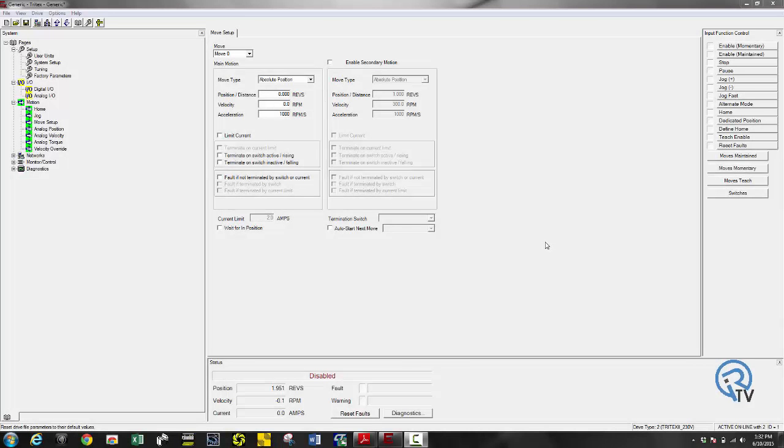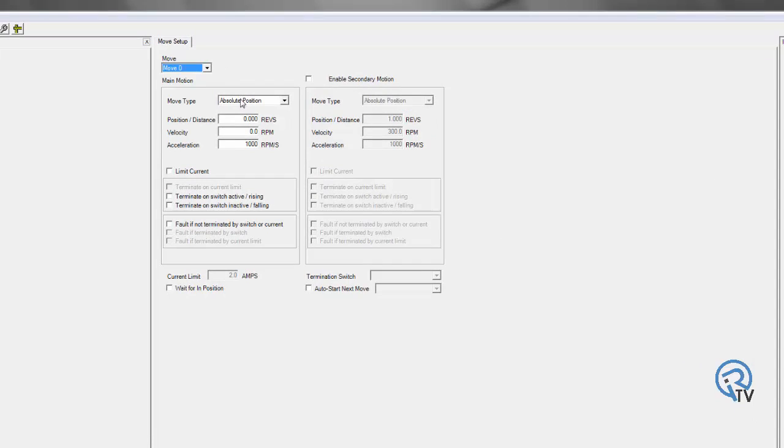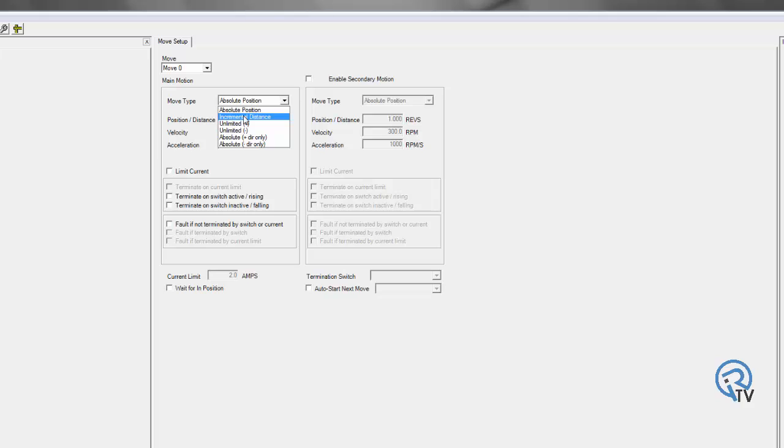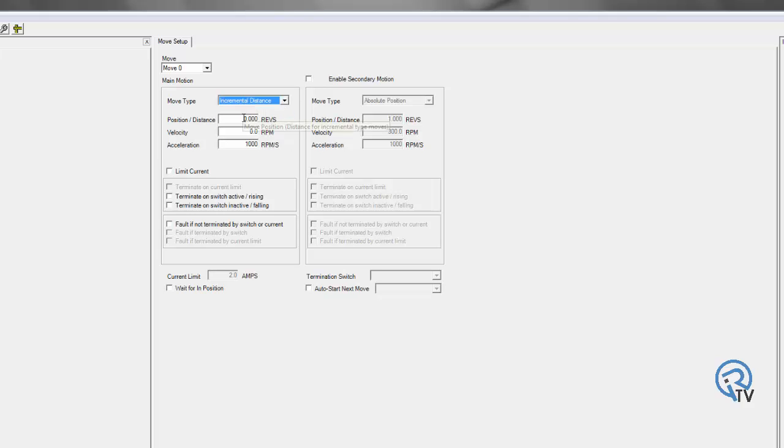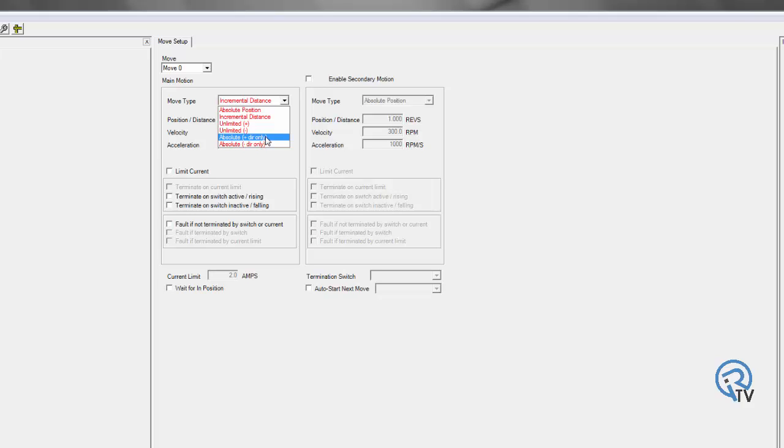Next thing I want to look at are my different types of moves. I can program up to 16 different move profiles. And they can be multiple types. One being absolute, which is a predefined position. I can do incremental. So I move at a specified distance, no matter where I'm at. I can do unlimited plus or unlimited negative. Essentially, this is forcing the drive to go either positive or negative. Or absolute plus or absolute negative, which is forcing the drive to go absolute position, either in the positive or negative direction.